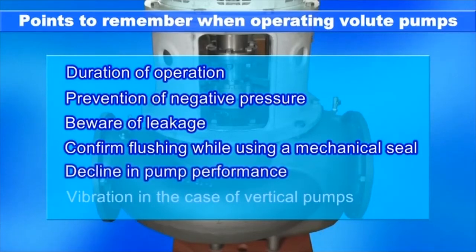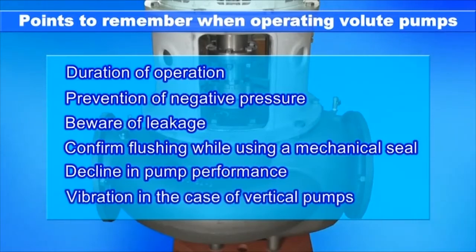Keep pressures always in mind and make a maintenance plan as necessary if a comparison of characteristic curves indicates a decline in pump performance. And with regard to a vertical pump, pay attention to vibrations that may affect shaft alignment.